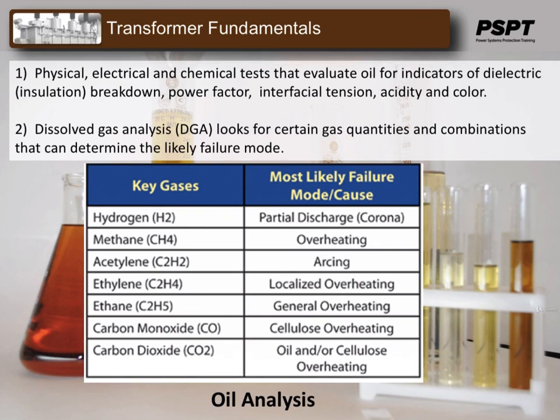Hydrogen indicates partial discharge, or corona, inside the transformer. Methane presence indicates overheating, and acetylene would indicate arcing presence inside the transformer. Ethylene would indicate the most likely failure to be in localized overheating, whereas ethane would indicate a general overheating of the unit. Carbon monoxide indicates cellulose overheating, which would be the wrapping insulation on the windings itself could be breaking down. And carbon dioxide would indicate that the oil and/or cellulose would be overheating.